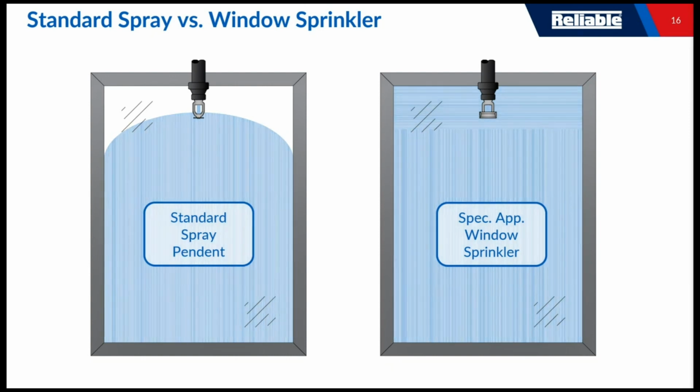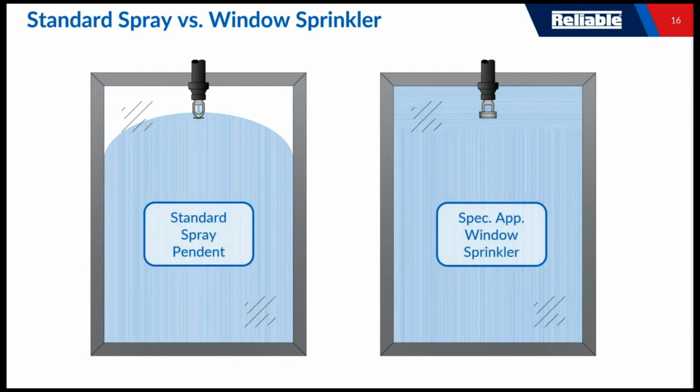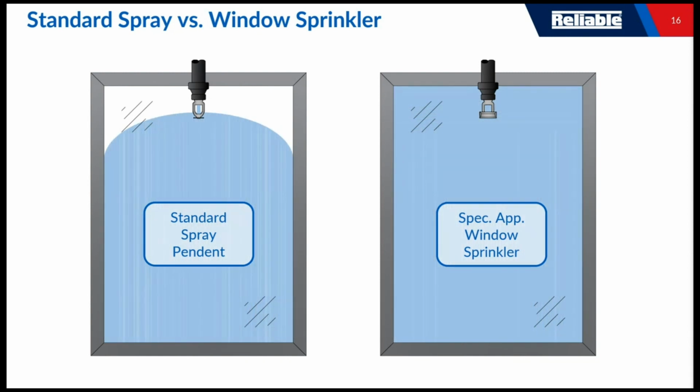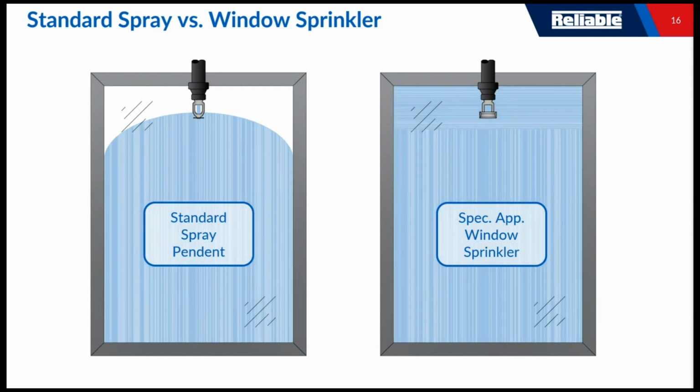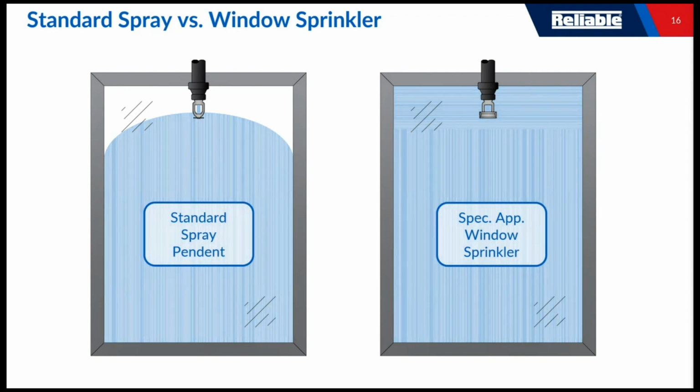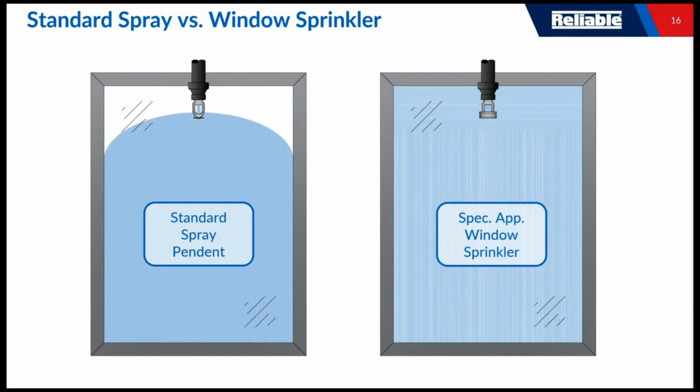If there's any dry spot in that glass, that allows the smoke and heat from a fire to heat that glazing material, and then you get into a situation with thermal shock with the cool water, and it will end up causing a crack and a failure in that glazing material. So I just can't stress how important it is to completely cover that window surface.